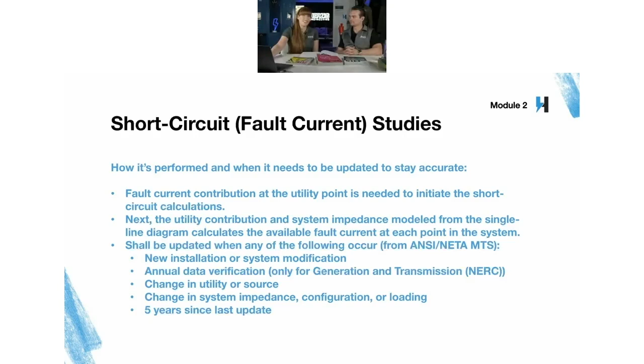All right, what do you do with the information? Why is a short circuit or fault current study so important? Well, first of all, what we like to look at is the available fault current for arc flash purposes. Yep. We'll get into that later when we cover the arc flash study. But short circuit studies are actually required to even calculate arc flash incident energy. Correct. And then also we use the available fault current information to determine whether your overcurrent protective device or devices is rated to be in the system, which is actually an NEC code requirement. Right. The interrupt or the AIC rating.